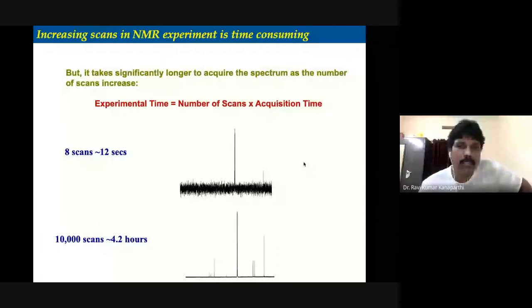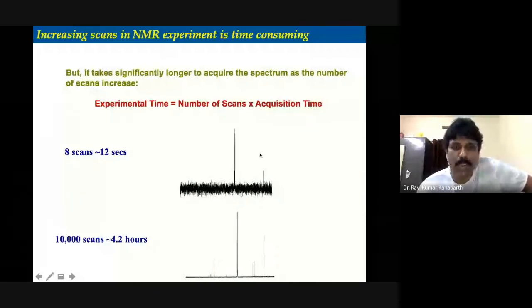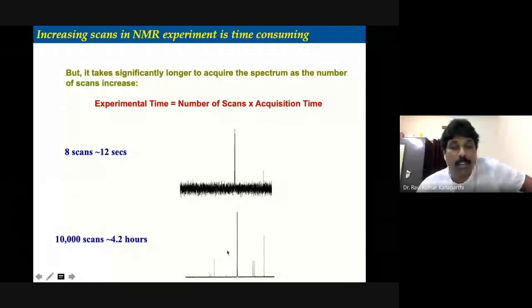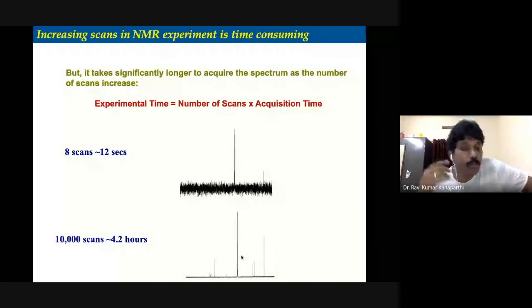For carbon-13 NMR, sometimes even 1000 scans are needed, depending on the molecule and its solubility in deuterated solvent. The whole idea is to improve the signal-to-noise ratio so that signals can be better understood. An example is shown: with 8 scans the carbon-13 NMR spectrum looks poor, but with 10,000 scans you get a much better spectrum where signals that were not visible before become apparent. When averaging a small number of scans, all signals may not appear, but with more scans all signals become visible.